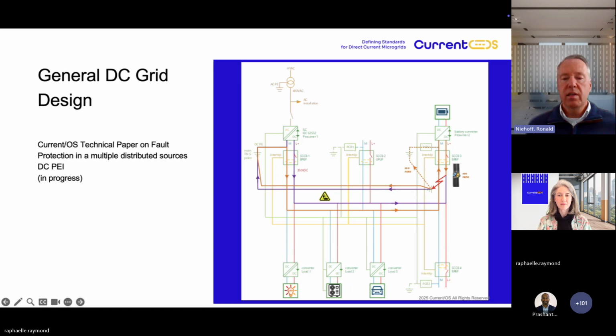So we are trying to cover all the short circuits between live and midpoint, and the short circuit from live to earth, so ground fault, both high ohmic and low ohmic. A high ohmic fault to earth could also be a protection or a direct touch situation, and we'd like to protect all types of faults for DC prosumer electrical installation.